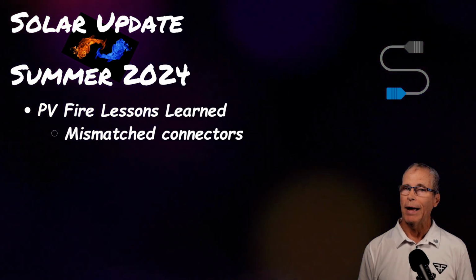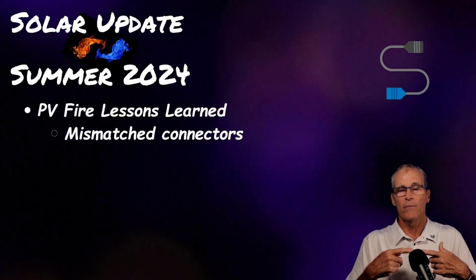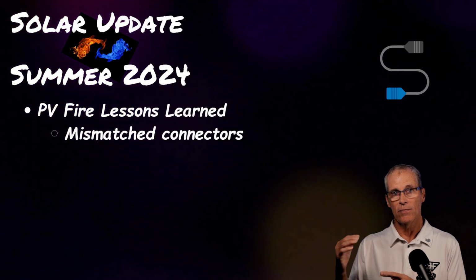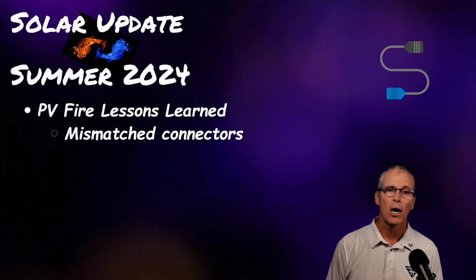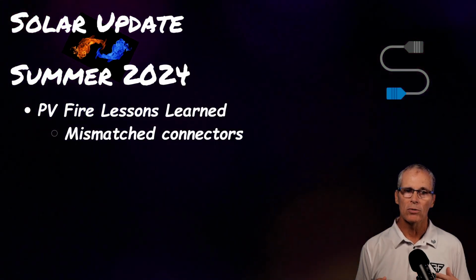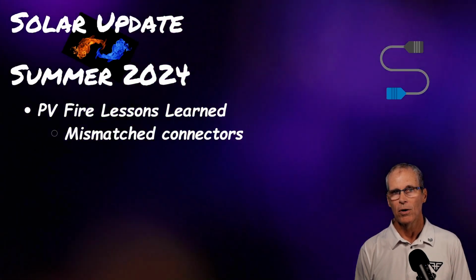And back in the past, it was possible that you could have two MC4 connectors made by different manufacturers. They could go together, it all worked. But what we're seeing now is that arrangement can lead to hotspots and failures in the future, which could be fires. So the issue needs to be addressed. Do we need to go out and replace all of these components with manufacturer-matched connectors? No, we don't need to go out and do that.